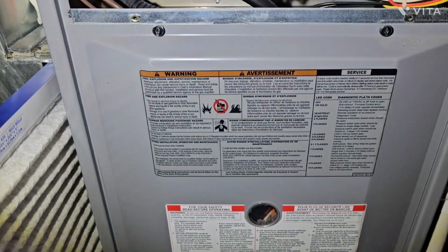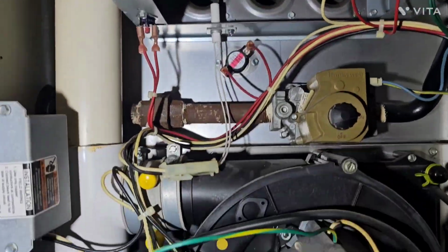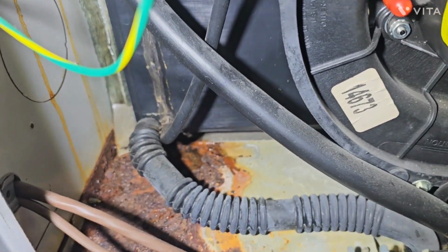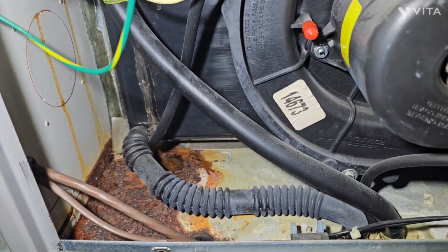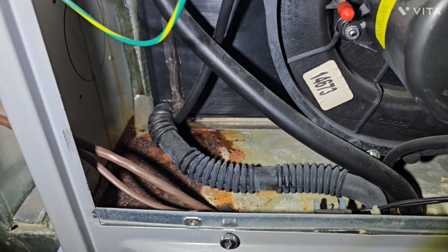If you can imagine, the cabinet is blowing air from down under here, blowing it up around the combustion chamber, but not through this area. It's not supposed to be in here. And if that burns a hole through there, now you're going to have some air blowing up into the combustion area, and who knows what it might do then. So we want to catch these drips before they create too much damage.